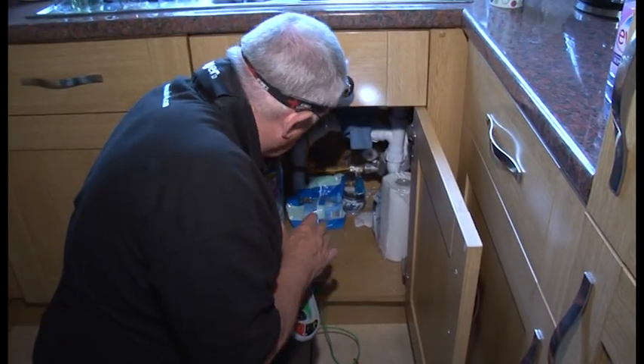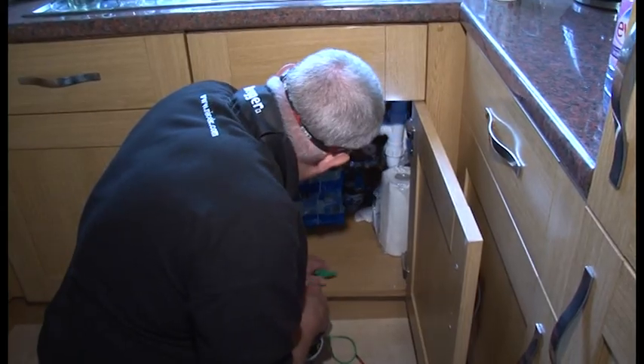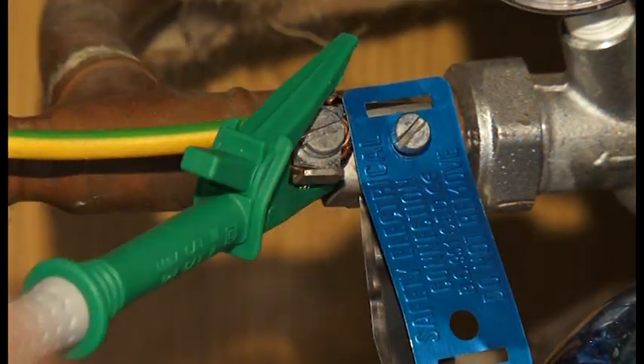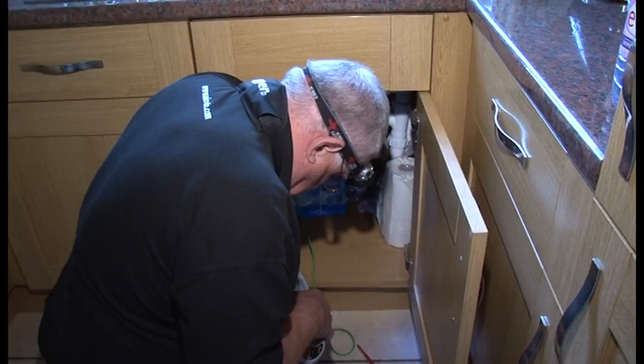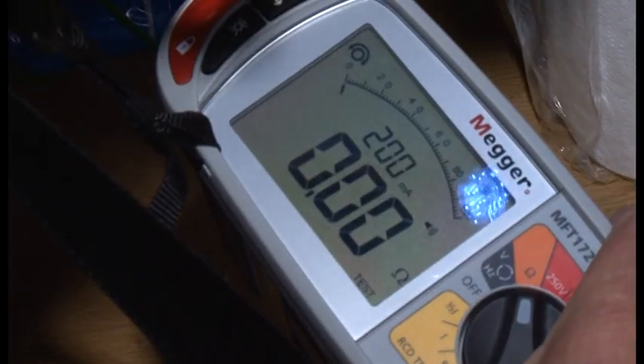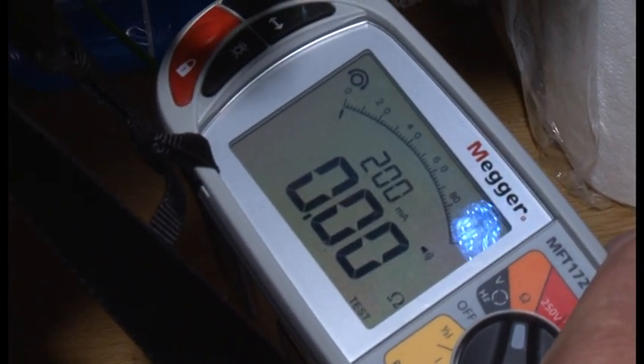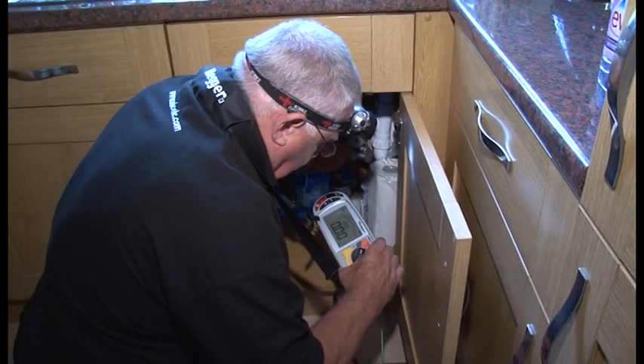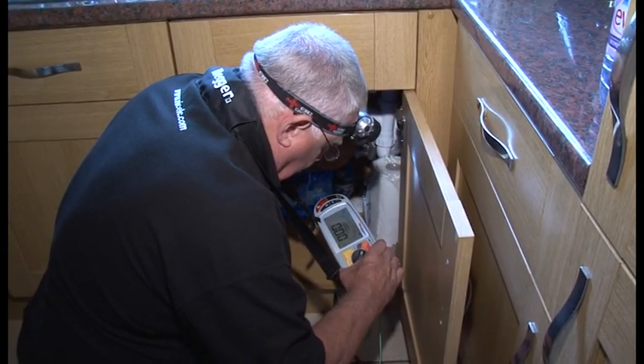Right, well here we are at the water, and we're going to test for the main equipotential bond to the water. And here we are, I've actually got a reading of 0. Now, what we've got to consider, of course, is this acceptable? What Tony is referring to here is that it's vital not just to accept readings at face value, even if they are lower than any value required to comply with the regulations.